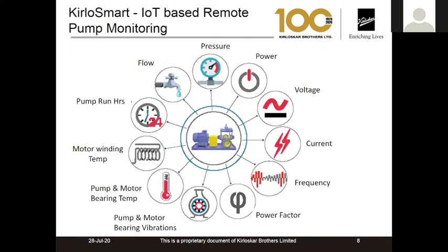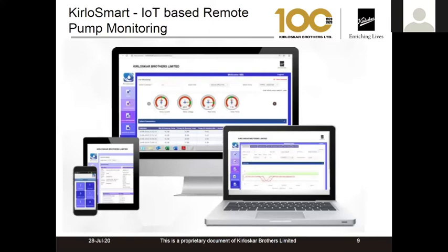The parameters we can monitor are, majorly for all pumps and motors: flow, pressure, power, voltage, current, frequency, power factor, pump and motor bearing vibrations and temperatures, motor winding temperature, and run hours. So in all, it can cover all the motor and pump parameters which need to be monitored by the customer. And as a facility, customers can get various visual dashboards and meters, so they can view and take note of all the readings, as well as manage the systems remotely.